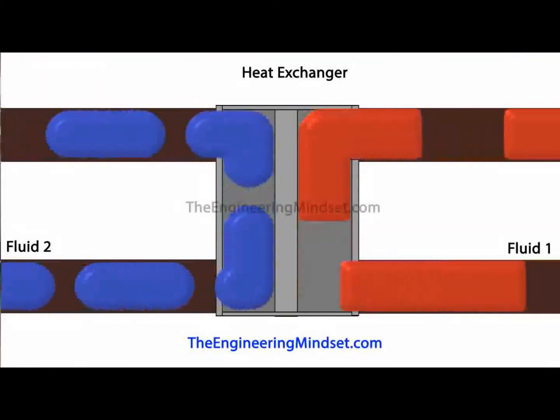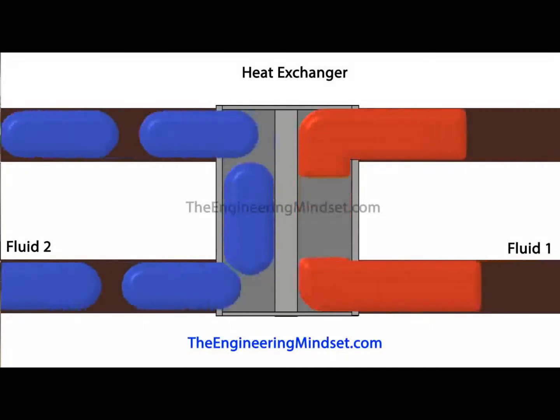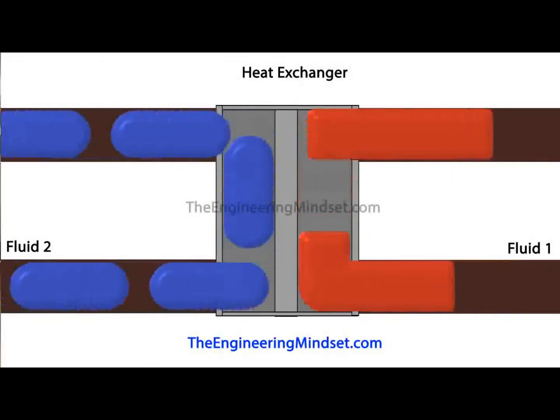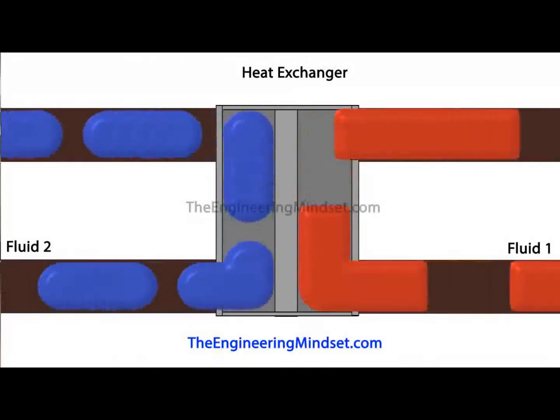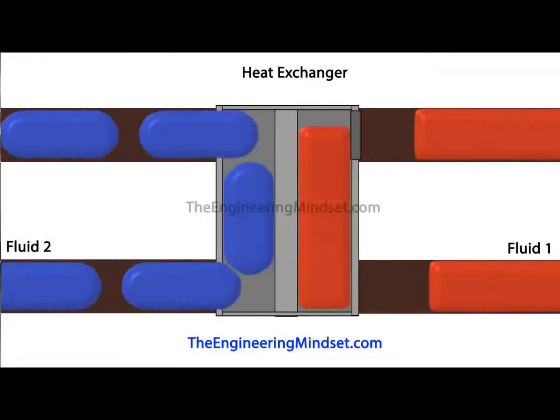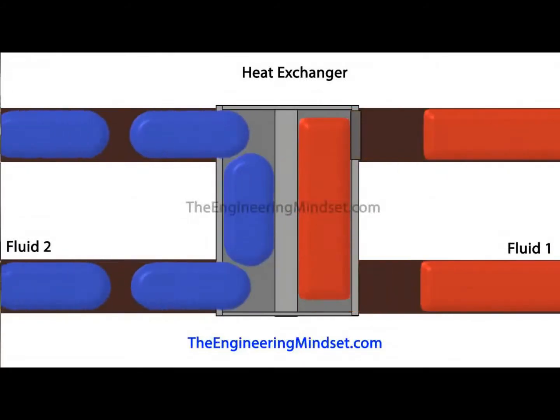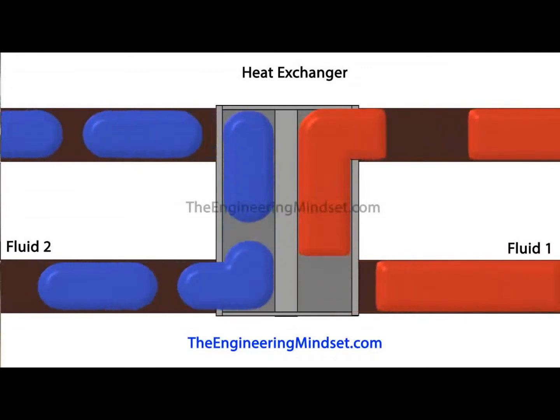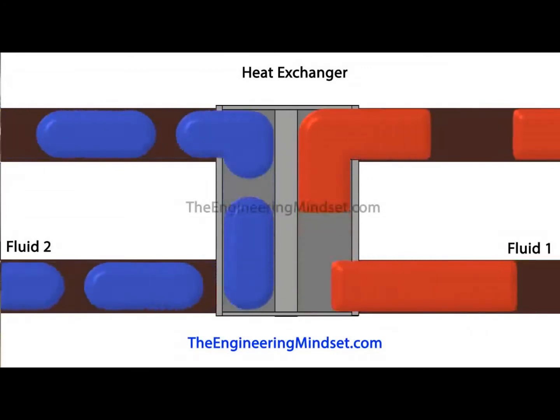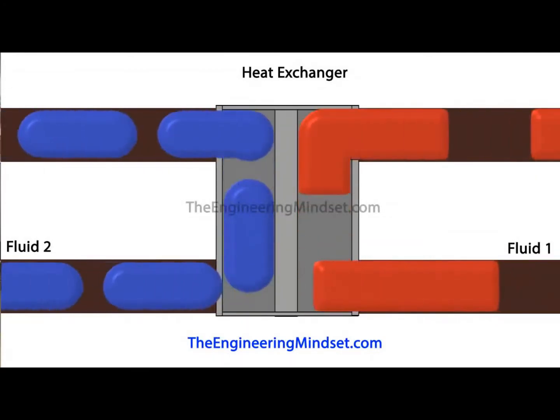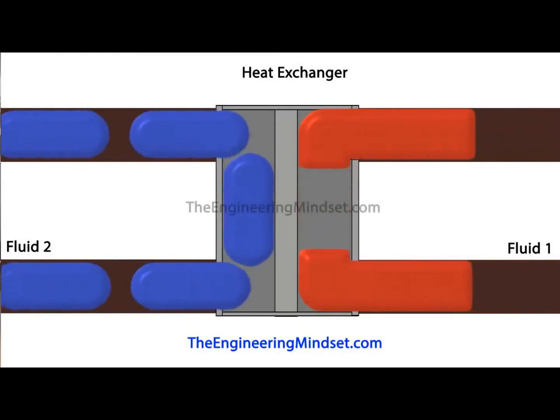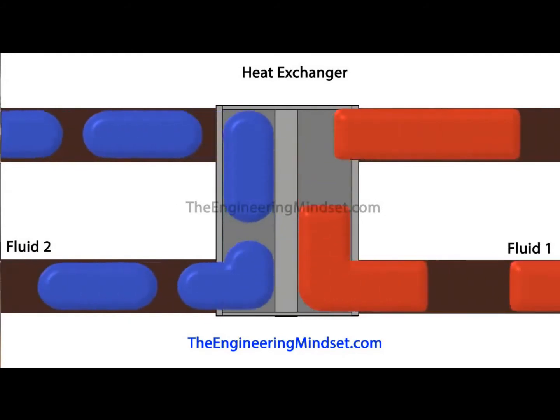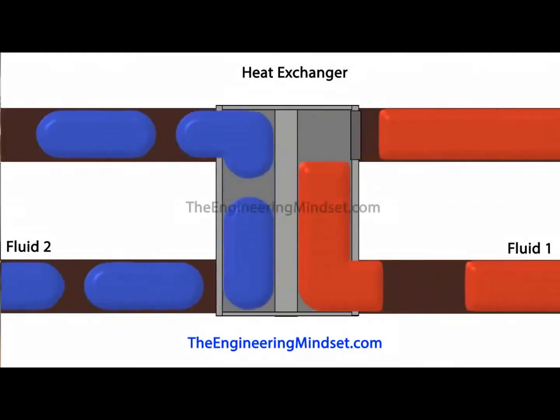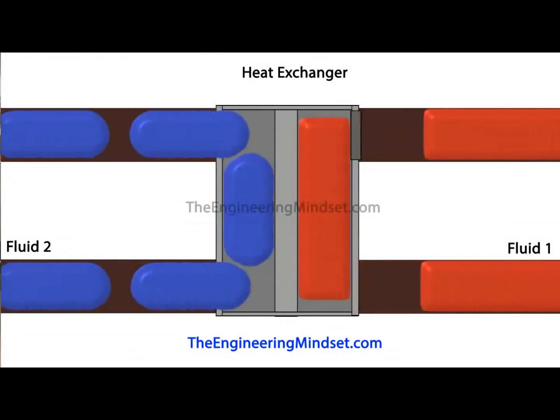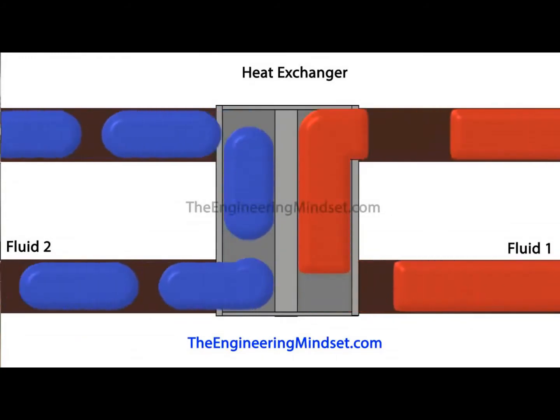Their purpose is to transfer thermal energy from one fluid in one system to another without the two fluids mixing together. For example, in building services, you might transfer heat from a primary loop connected to a boiler over to a separate secondary loop, or maybe in a district heating network. Or in manufacturing, you may want to cool down some oil using water, but obviously you don't want to mix the oil and water together.